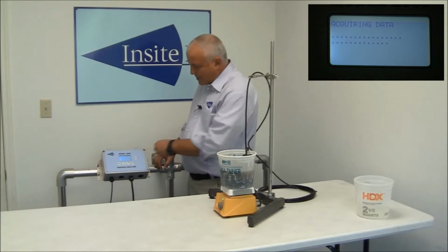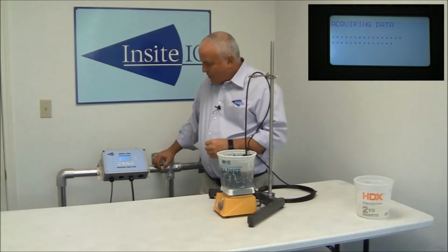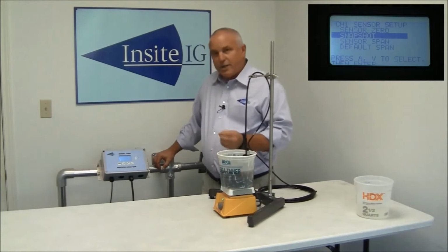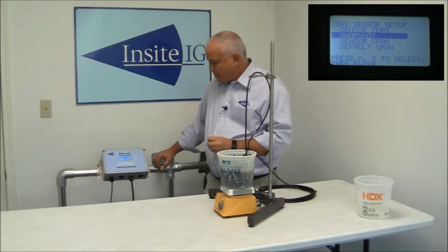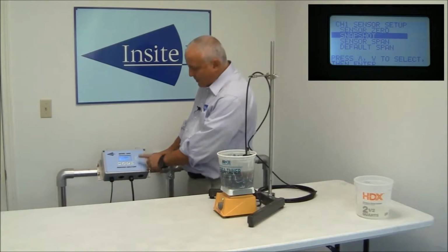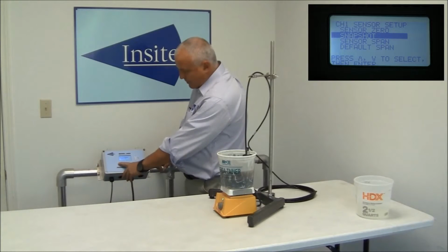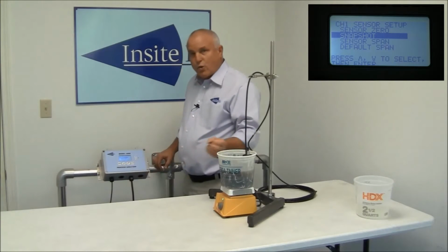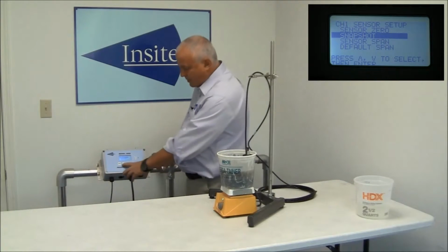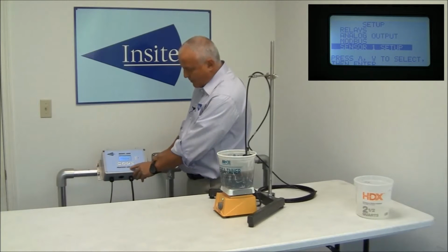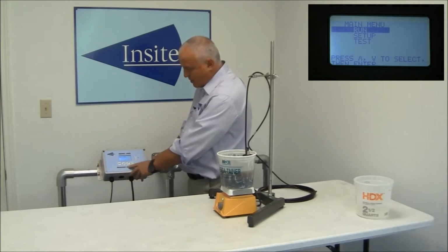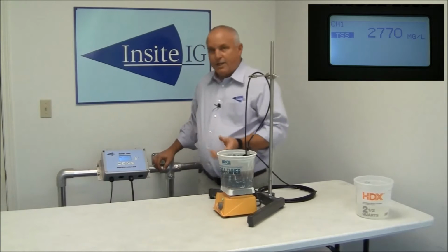As you can see, there's dots along the display. Once it finishes, it's going to come up with a number it thinks it is based on its last calibration. So it comes back to the menu. It's already stored that new number. So you hit menu, go back to run, and it just runs.